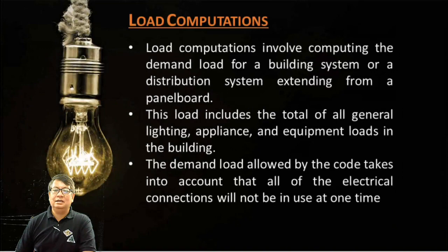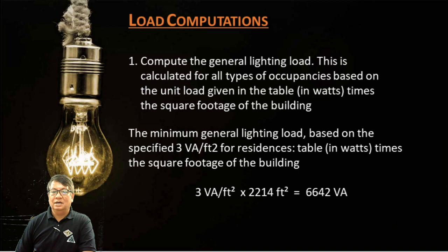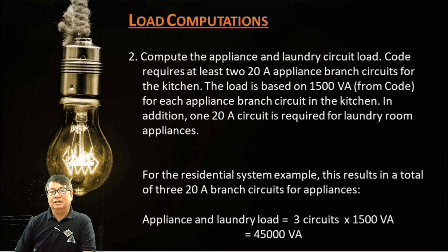So load computations na tayo. So we have here mga load computations natin. We have this 3 volt-amperes per square foot. Ito po yung minimum general lighting load requirements. So halimbawa, if yung area natin is 2,214 square feet, then multiply it by the specified lighting minimum, which is 3. More or less with that area of 2,214, we need 6,642 volt-amperes.